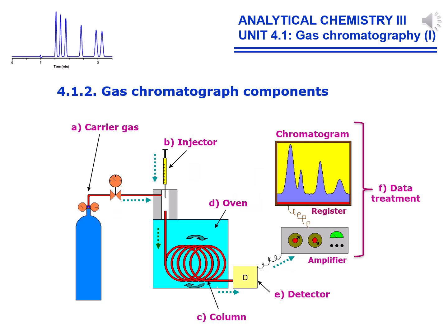A general description of the process is indicated by the arrows in the slide. The sample is injected through a rubber septum into a hot injector, coated with glass or metal, where the sample is vaporized. The sample is pushed by a carrier gas stream into the column, which is inserted in an oven. By a rise in the temperature, the sample components are separated and finally reach the detector, where the signal is recorded as a chromatogram.